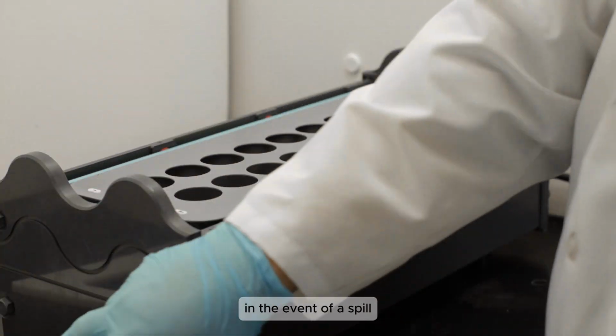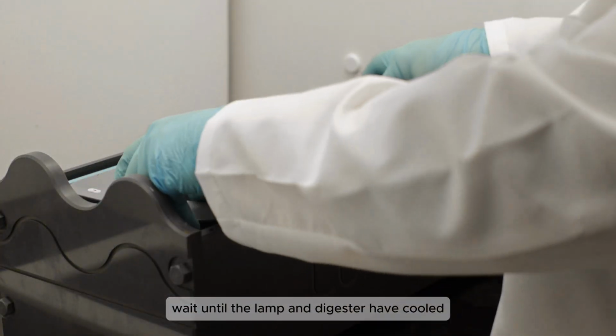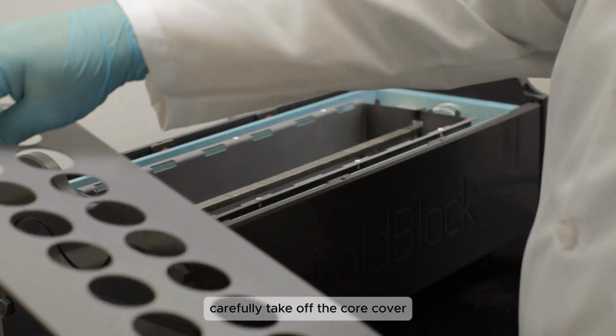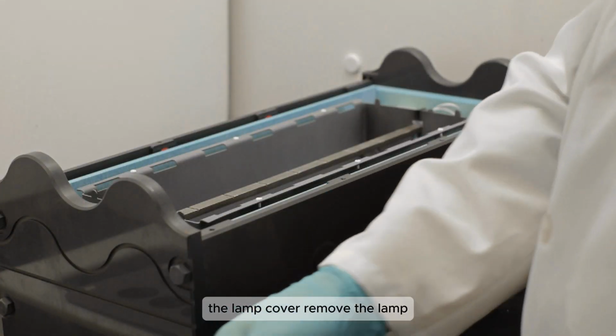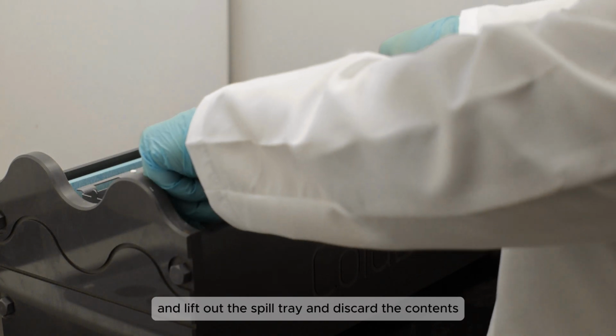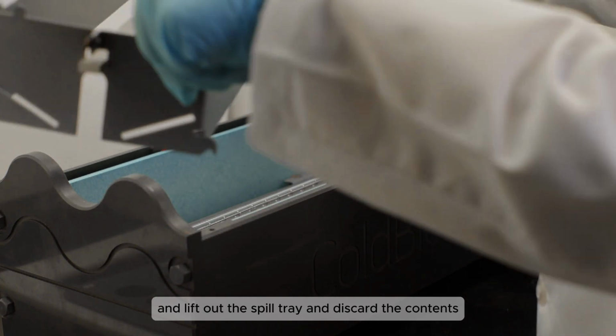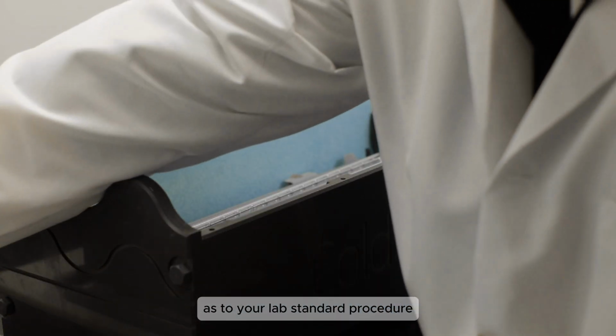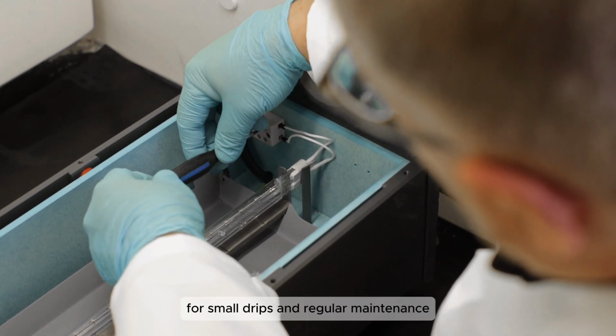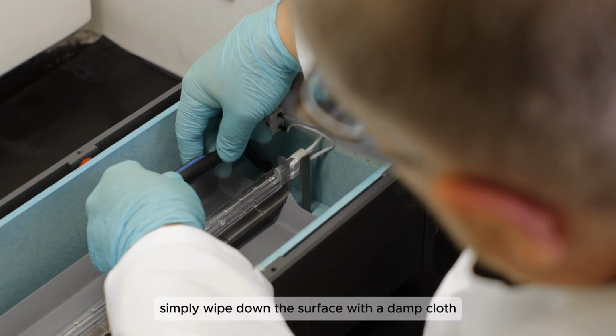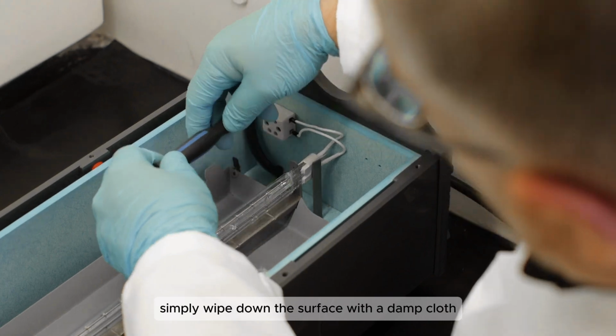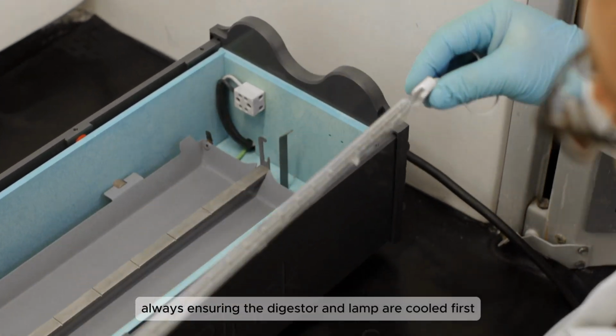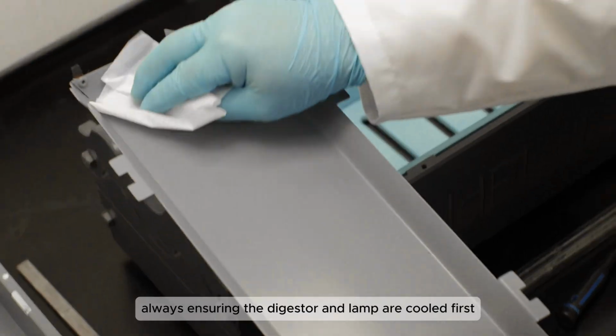In the event of a spill, wait until the lamp and digester have cooled. Carefully take off the core cover, the lamp cover, remove the lamp and lift out the spill tray, and discard the contents as per your lab's standard procedure. For small drips and regular maintenance, simply wipe down the surface with a damp cloth, always ensuring the digester and lamp are cooled first.